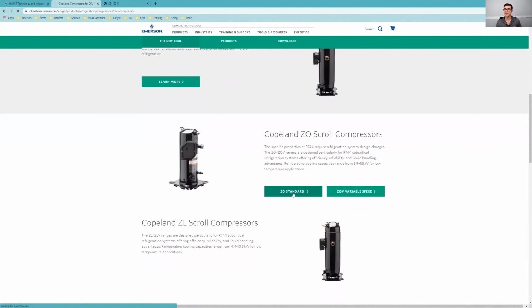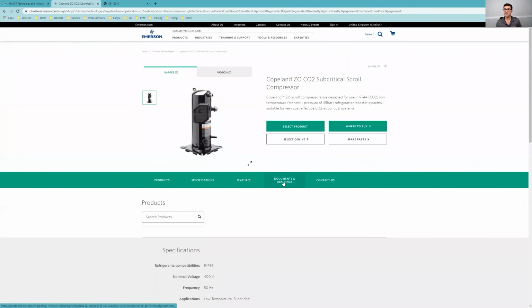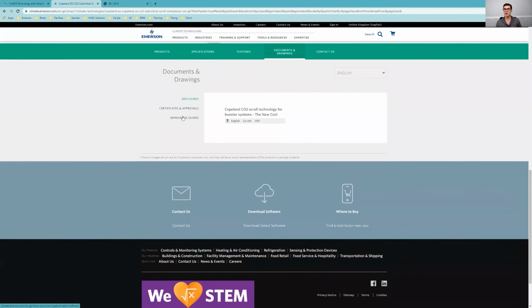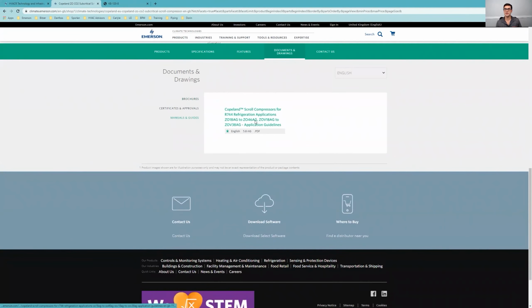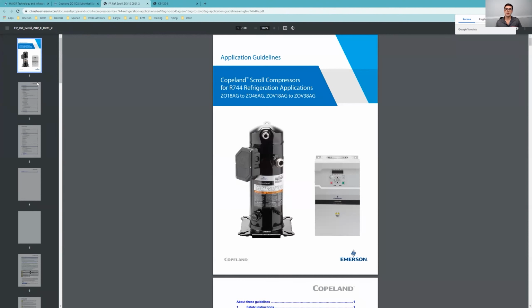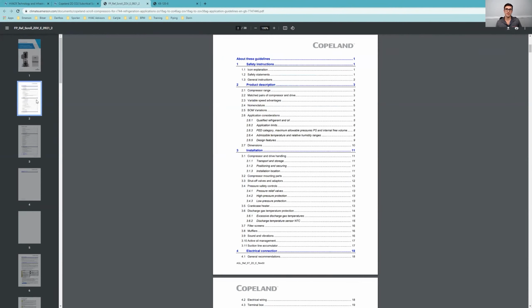But we'll do the standard ZO. And then you go to documents. So whatever compressor you want, manuals and guides. And here it is. This is talking about their new ZOV with their new drive and stuff. And here's so much good content. Over time, after you read more and more of these, it gets easier, because you see a lot of similarities from the other manufacturers. Understanding the superheat, the discharge temperature, the amps, the operating envelope of the CO2 compressors.